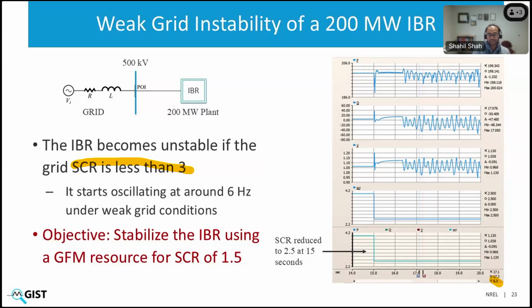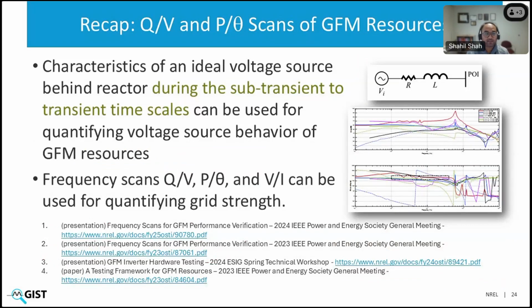Now, to size the grid forming resource, we need to have a defined objective. So the objective that we have is we want to stabilize this 200 megawatt IBR plant using a grid forming battery storage at the POI so that it can operate stably when the SCR is 1.5. So how do we do that?